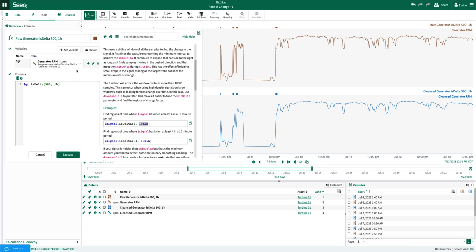In my case, I applied this against the raw generator RPM and the cleansed RPM, with the magnitude being 500 and the period being 1 hour. Which means, within a rolling 1 hour basis, any time this signal has increased by 500, I want it to be identified.